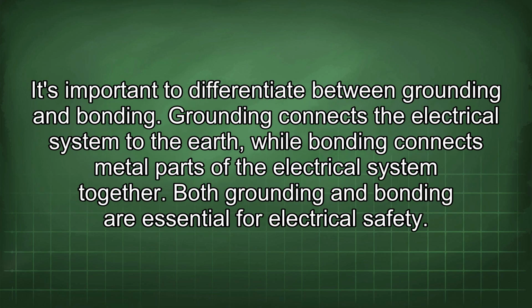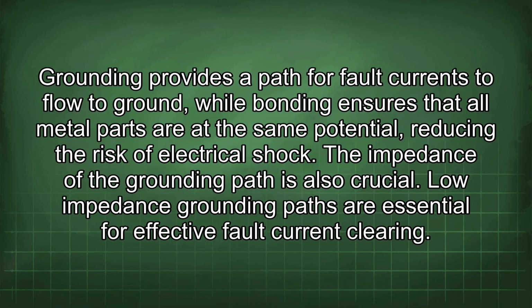It's important to differentiate between grounding and bonding. Grounding connects the electrical system to the earth, while bonding connects metal parts of the electrical system together. Both grounding and bonding are essential for electrical safety. Grounding provides a path for fault currents to flow to ground, while bonding ensures that all metal parts are at the same potential, reducing the risk of electrical shock.